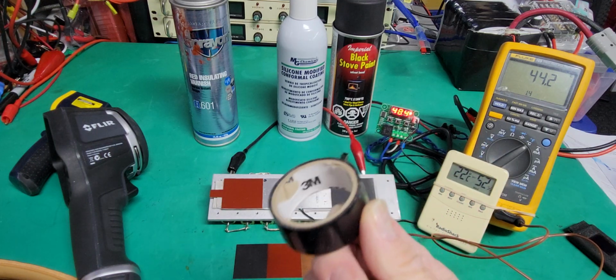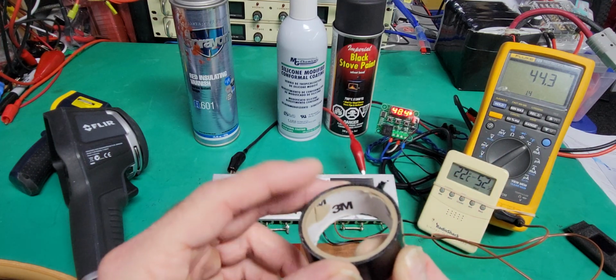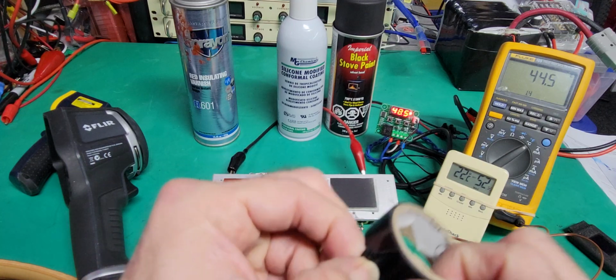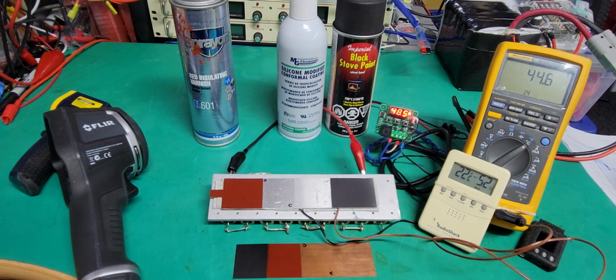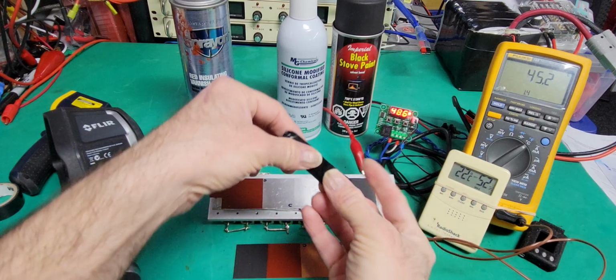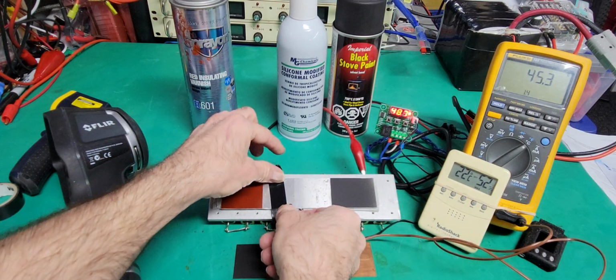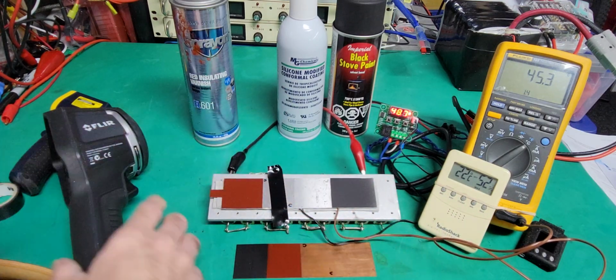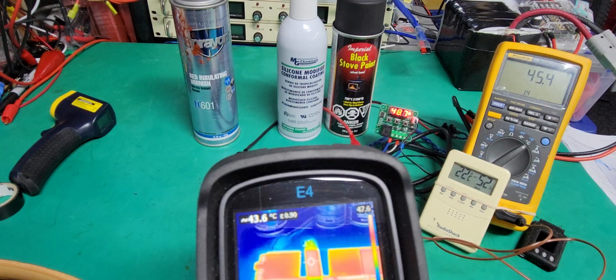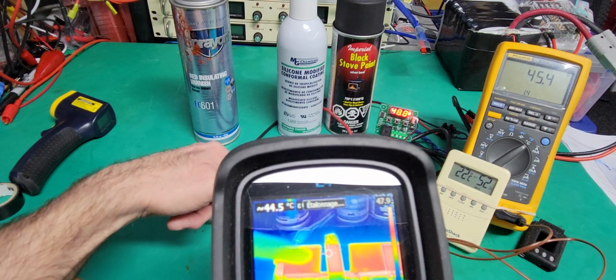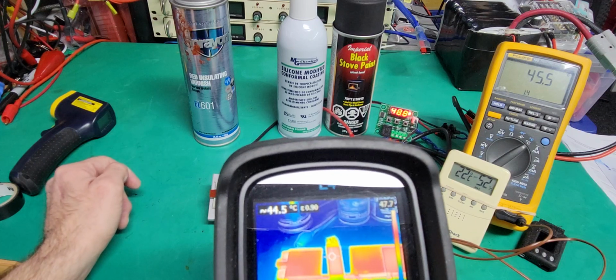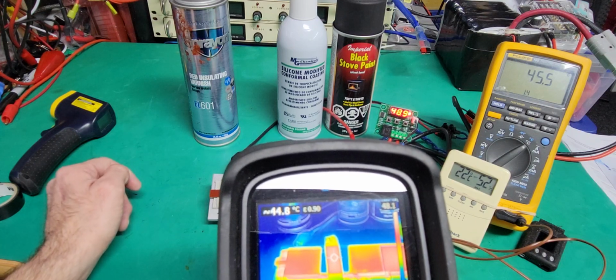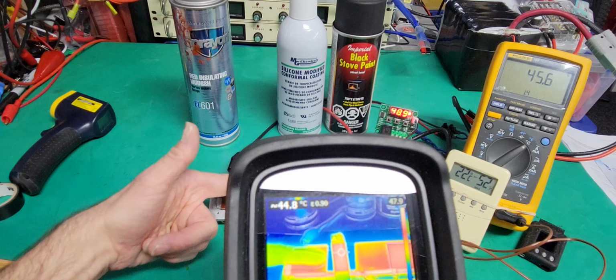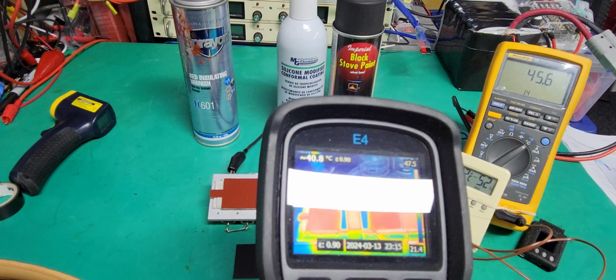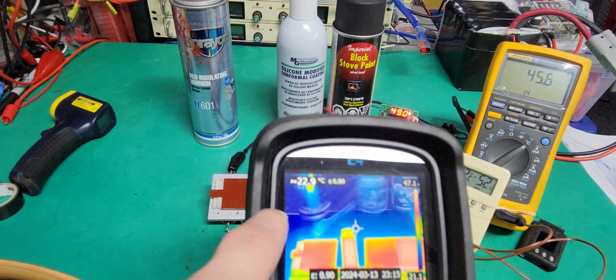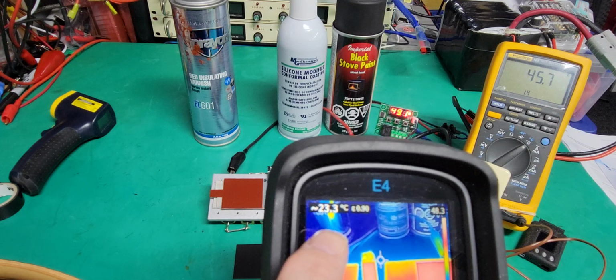This tape here, this is electrical tape. It's very well known for thermography. You can use just a small piece, just like that. And if you put it on the shiny surface of a bare aluminum with no coating, check what's happening. So you see the piece of tape right here, and you see the temperature, 44 degrees Celsius. So that is great, it's actually working. So right now the emissivity of this tape corresponds very closely to the emissivity setting of the camera, and it can read the number perfectly here.